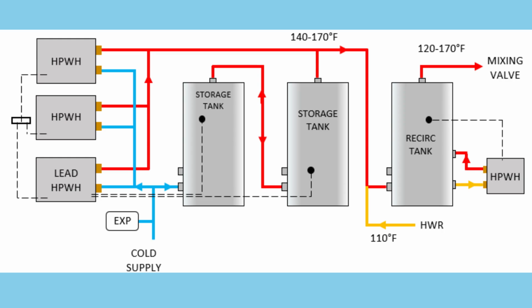In summary, single-pass HPWHs paired with dedicated temperature maintenance systems deliver the best efficiency. Swing tanks are simple and cost-effective, while parallel loop systems are better for high recirculation losses. Return to primary systems are familiar but less efficient, especially in multi-pass setups.